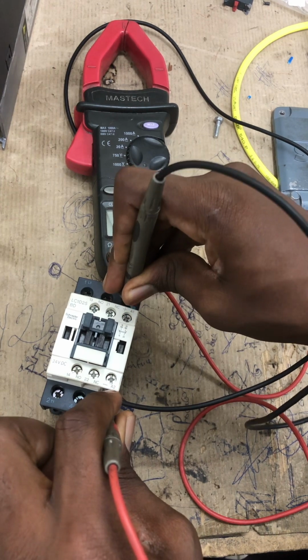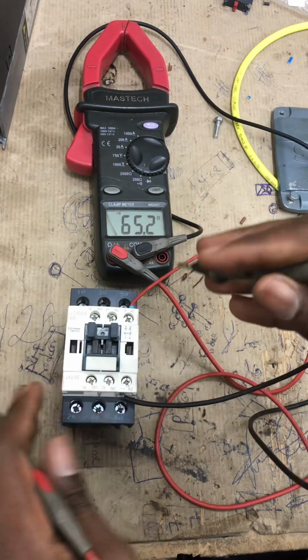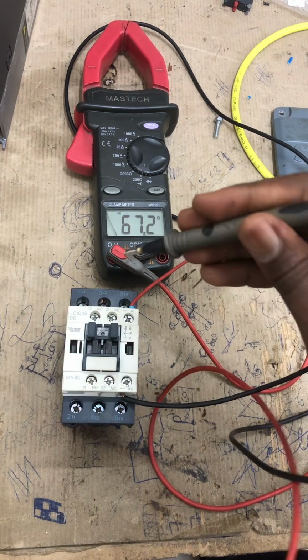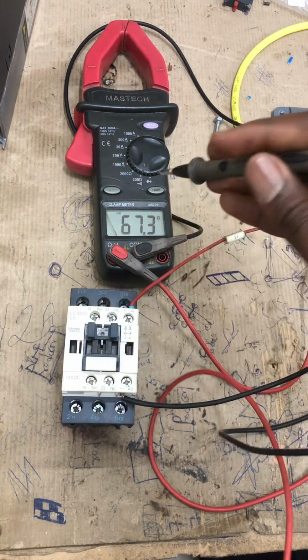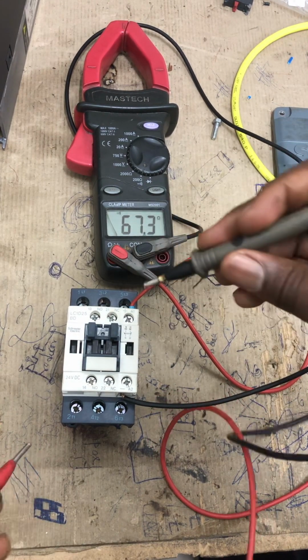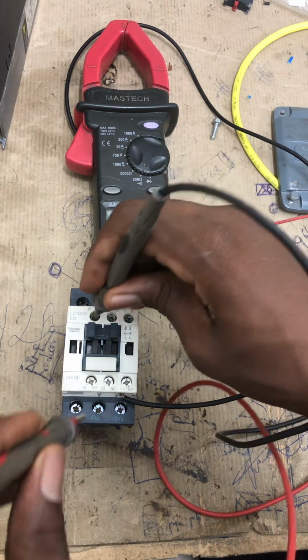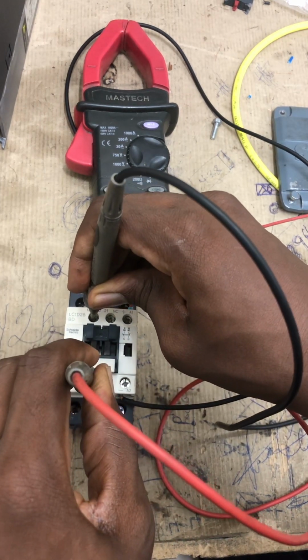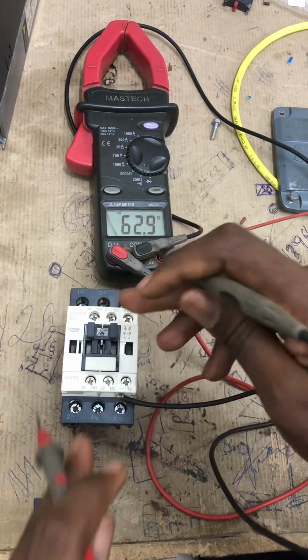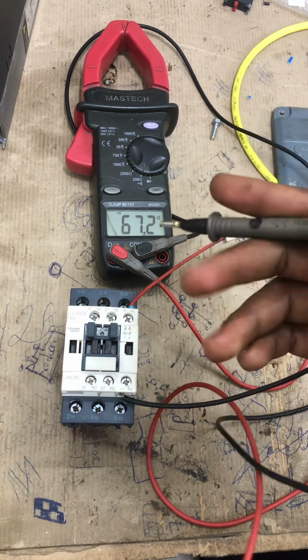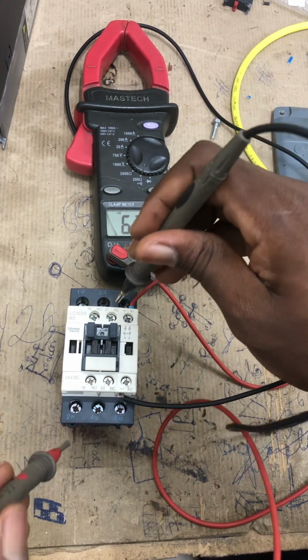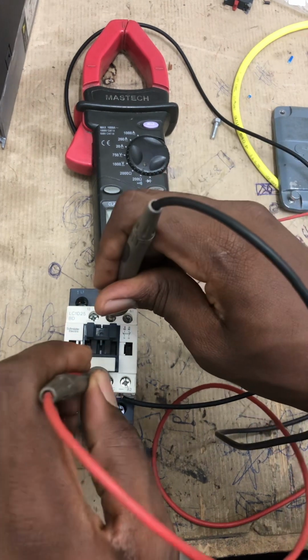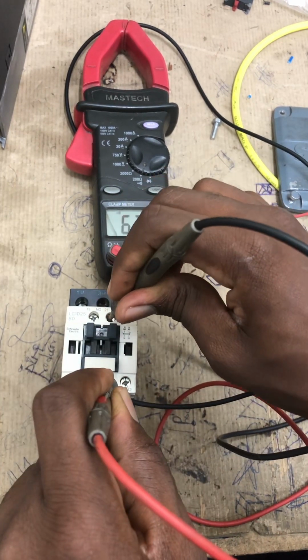So that's it for lines 5 and 6. And then the auxiliary contacts: 13, 14 is normally open, but when the coil gets energized, it becomes closed. 21, 22 is normally closed, but when the coil gets energized, it becomes open. So no beeping sound here.